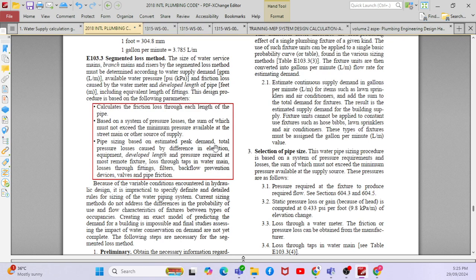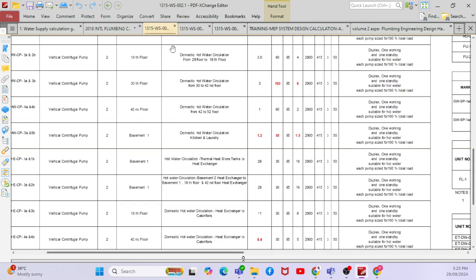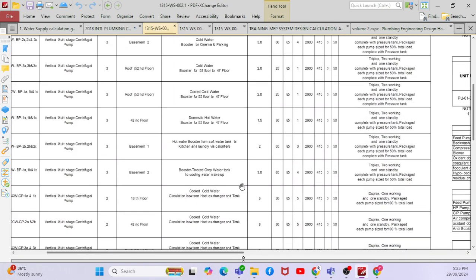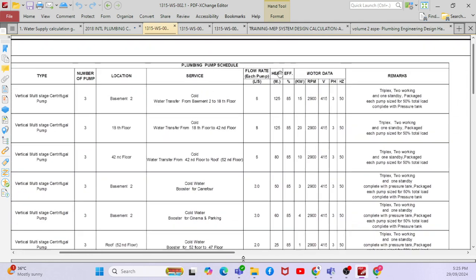Only then can you calculate the pump head. If you go to one of the equipment schedules, you can see the pump head in meters — for example, 125 meters. They calculated this for each fitting, each pipe length, static pressure, and the foremost fixture: the pressure required at that particular fixture and the residual pressure. The summation of all this gives you the total pressure, which is the pump head calculation.